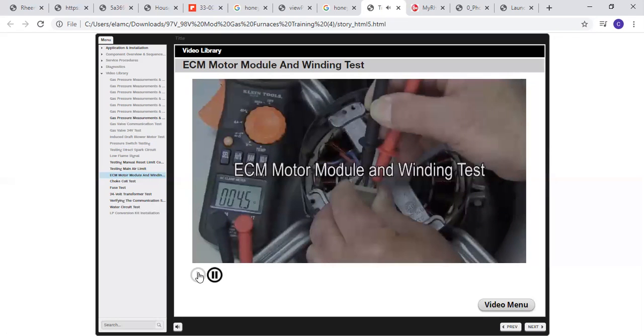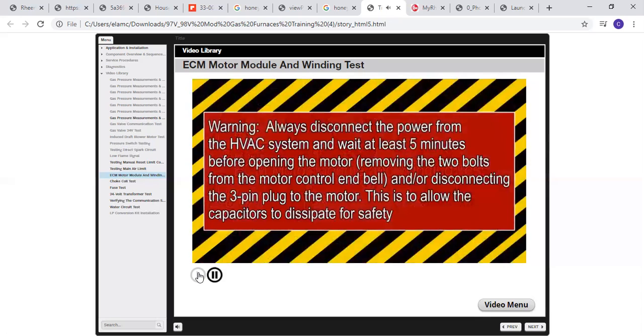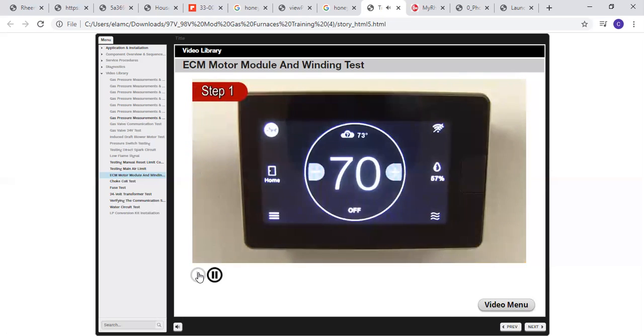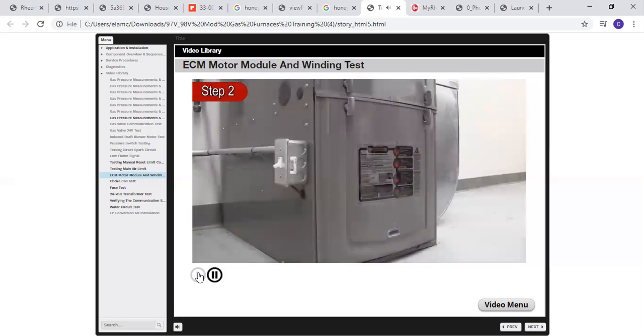ECM motor module and winding test. Warning: always disconnect the power from the HVAC system and wait at least 5 minutes before opening the motor, removing the 2 bolts from the motor control end bell, and/or disconnecting the 3-pin plug to the motor. This is to allow the capacitors to dissipate for safety. Step 1. End any calls for furnace operation. Shut off power to the furnace.